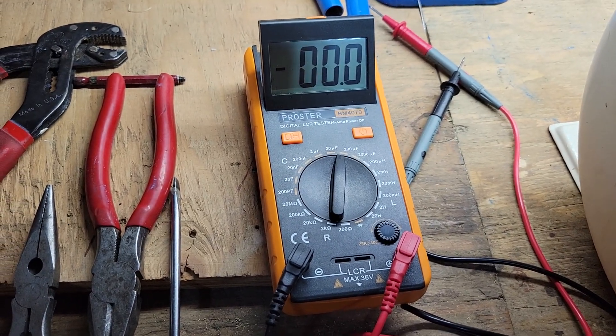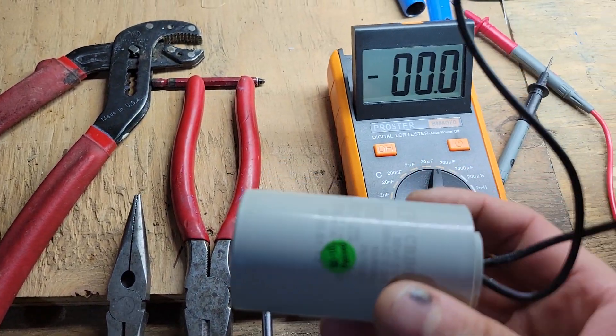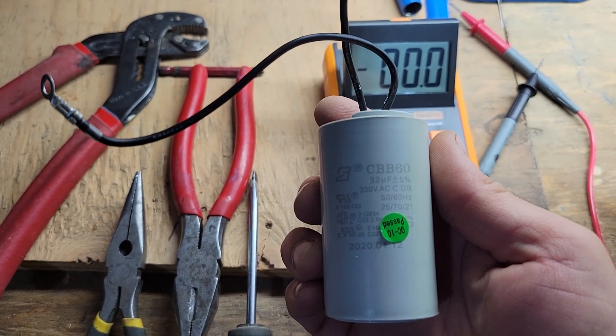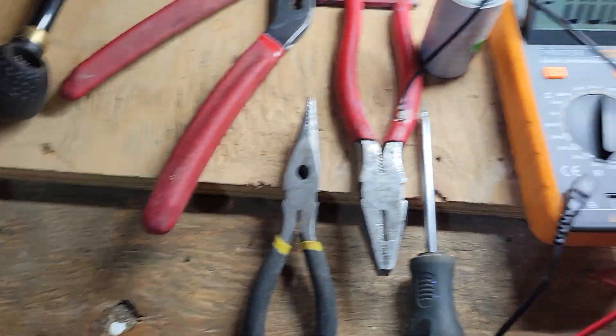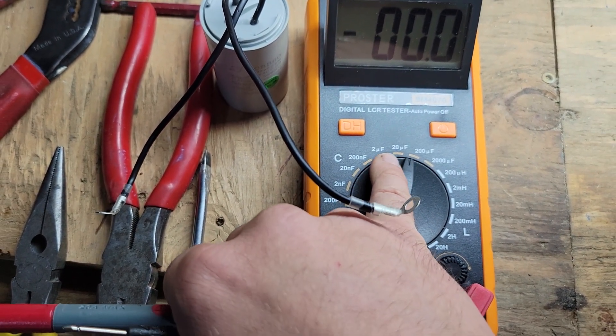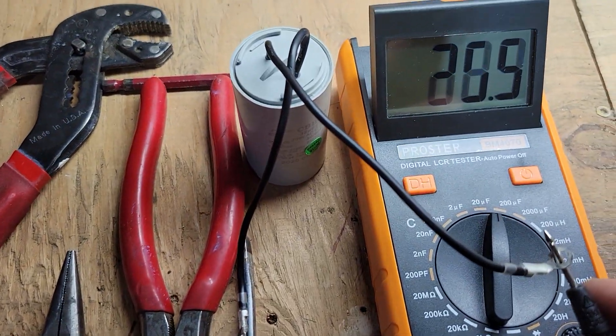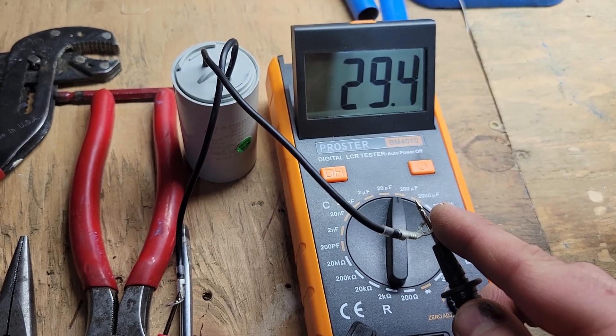Once you take it out to test it, you need an LCR tester — one of these, easily picked up on Amazon for around 50 bucks. It measures capacitance. The info on this capacitor: 32 microfarads, 300 volt AC, made in 2020. I set it a little higher than 20, which puts me at the 200 range, then hook up the leads one here, one here.